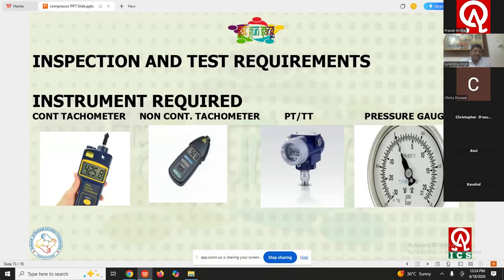This was the earlier, conventional method. When we are going to check the RPM, we need to put the contact surface physically on the rotating part. So it gives wear and tear. That's why nowadays this instrument is avoided, and the non-contact type is used. How does this work? We put a tape or any sensing paper on the rotating pulley. The sensor senses this tape rotation through a laser. In 1 minute, how many times the tape crosses the sensor is automatically calculated, and the RPM is shown on the display.